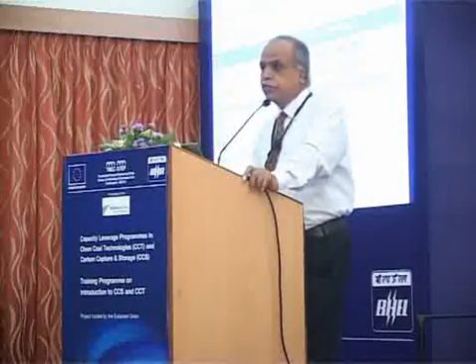And then we come to the oxygen. The oxygen here is approximately 11.2% of the flue gas, and in the product we need only 150 ppm. So we don't need any additional facilities because these solvents are very selective for CO2. The solvents reject oxygen along with nitrogen. That solvent has an affinity only for polar components. CO2 being a polar component gets accepted along with the solvent, and O2 and others are removed via the flue gases. Like if you see here, the exit gases, nitrogen and oxygen which are present, are rejected by this route. So no oxygen control is needed.